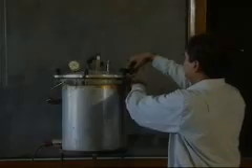Another important aspect of heat is that it coagulates the albumin of bacteria and causes them to die. It also destroys the enzymes of bacteria, and bacteria cannot carry out their activity further. For moist heat to be effective, two important points have to be kept in mind. All parts of the load should be in direct contact with water and steam. The temperature of the water should be above the boiling point. To build up this temperature, we need a pressure vessel, and this is called an autoclave.